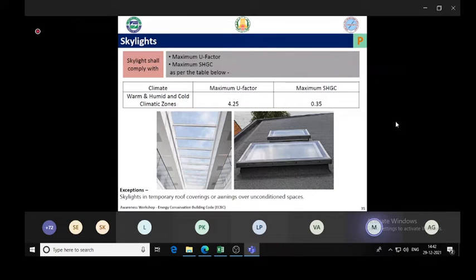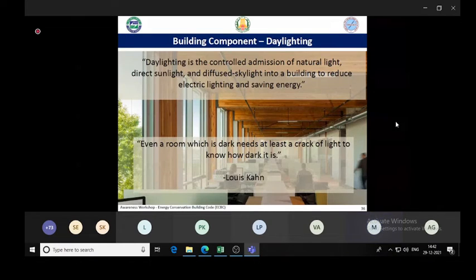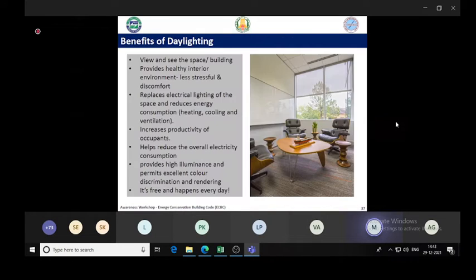Okay, like vertical fenestration, for skylights also we have U value and SHGC. U value should be less than 4.25 and SHGC less than 0.35. Now, looking at one of the very critical requirements in ECBC, daylighting. This is a mandatory requirement in ECBC 2017.